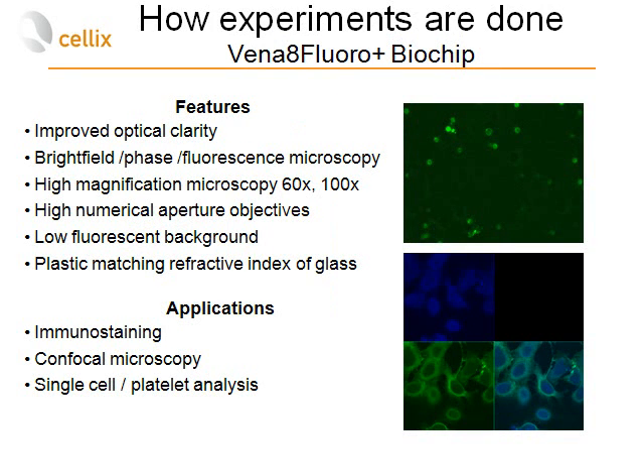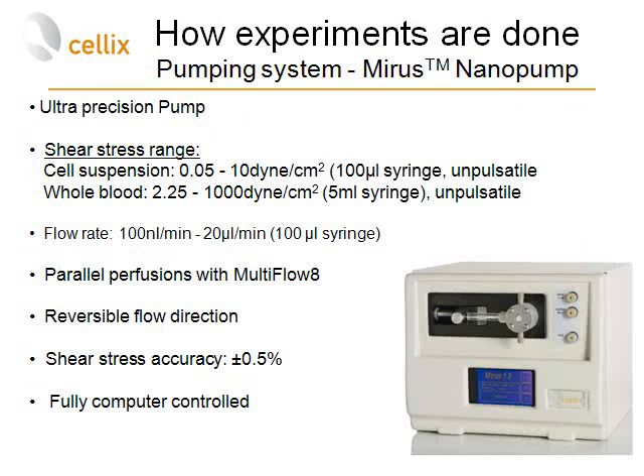As features of the biochip, it offers improved optical clarity supporting bright field, phase, and fluorescent microscopy. It can be used with high magnification objectives — 60x, 100x, and oil immersion objectives. It has very low fluorescent background and plastic matching the refractive index of glass. In applications, it can be used for immunostaining of cells, confocal microscopy, or single cell and platelet analysis.